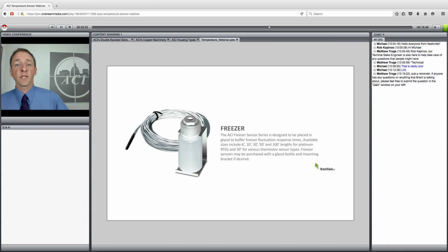On the low side, we have freezer sensors with thermal buffers, or these glycol bottles, and these are commonly used in coolers and freezers. The bottle is filled with glycol or some other type of thermal buffer, and it essentially just slows the response time. So if you have the sensor by itself in a freezer that, say, is 20 below zero, and someone opens the door to that freezer, the sensor gets a shock of room temperature air, it could send the system into alarm. Well, in this application, the probe is stuck inside of this bottle that's filled with a glycol or similar type solution, and it acts as a buffer to slow the response time, so it can more accurately react to the actual temperature changes in the freezer or cooler.